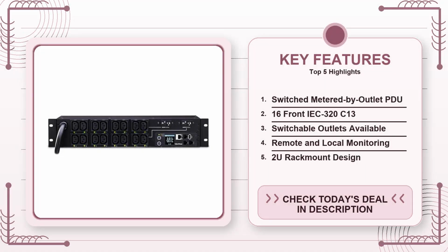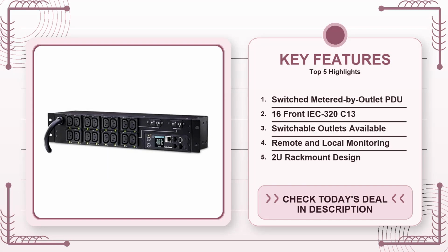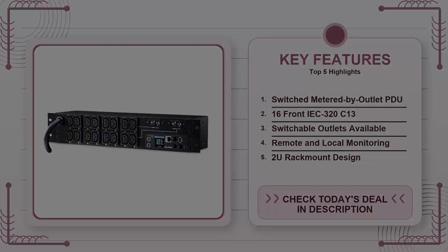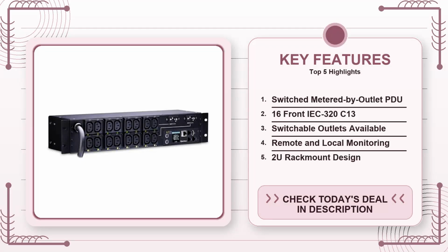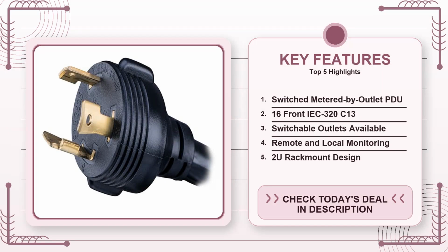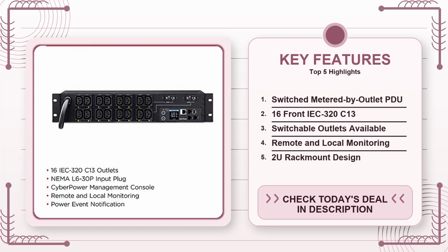If you're wondering about reliability, CyberPower has a solid reputation in the UPS market, and this PDU inherits many of the same design principles. The unit includes an internal overload protection circuit that will trip the entire device if you exceed the 24A limit, which is a safety net that many cheaper power strips lack. The switched outlets use mechanical push buttons that feel solid. They're not the flimsy toggle switches you might find on a budget strip.